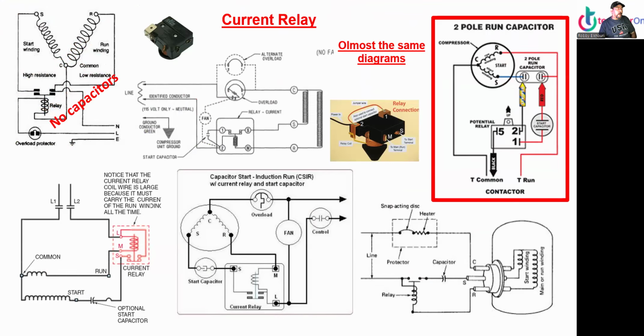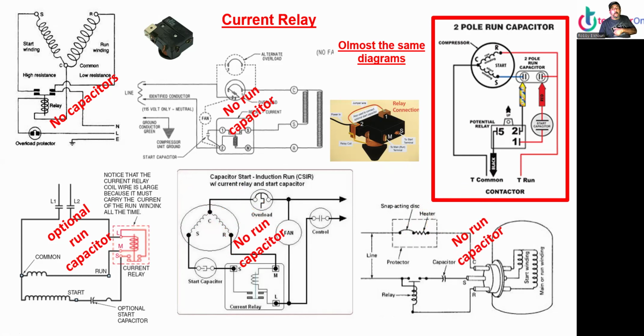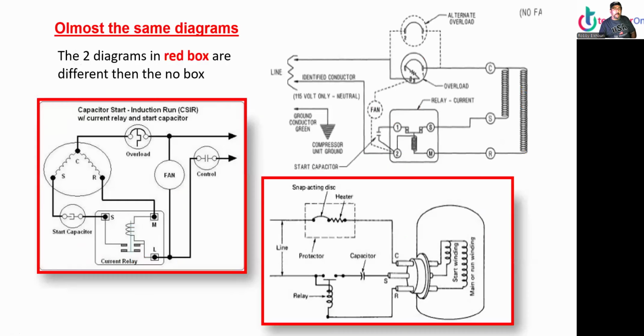That means capacitor start, induction run. This one has no run capacitor. This one has an optional run capacitor. It says it's optional. This one has no run capacitor. And this one has no run capacitor either. Most of the time it doesn't have a run capacitor, most of the time.